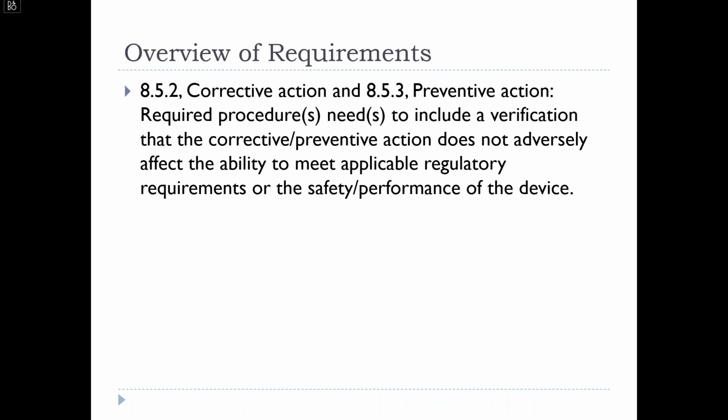And finally, 852, which is corrective action, and 853, which is preventive action. The required procedure here needs to include a verification that the corrective preventive action implemented does not adversely affect the ability to meet applicable regulatory requirements on the safety and performance of the device.